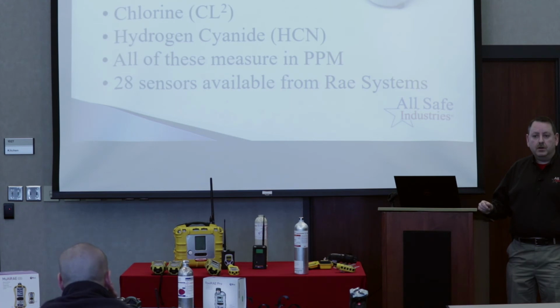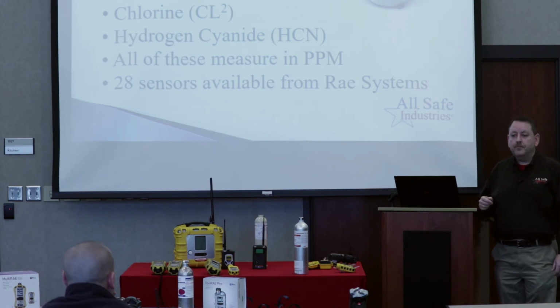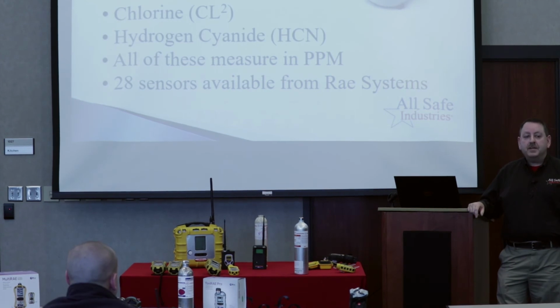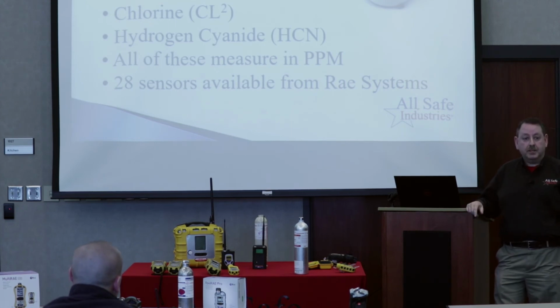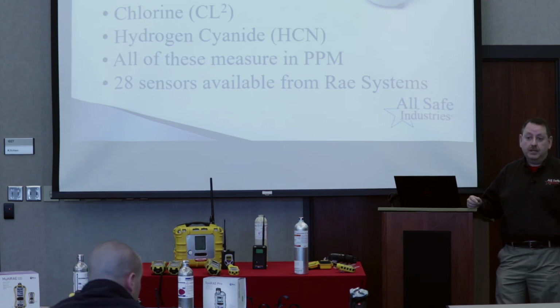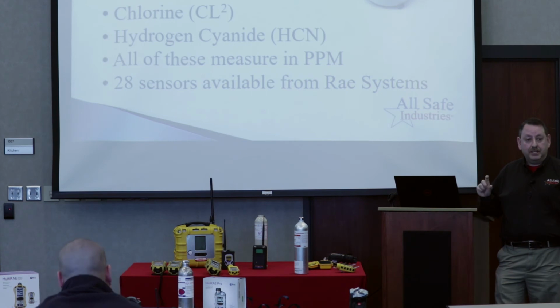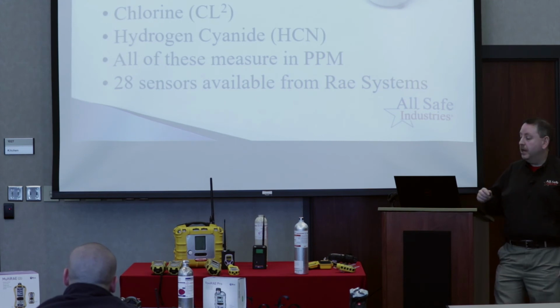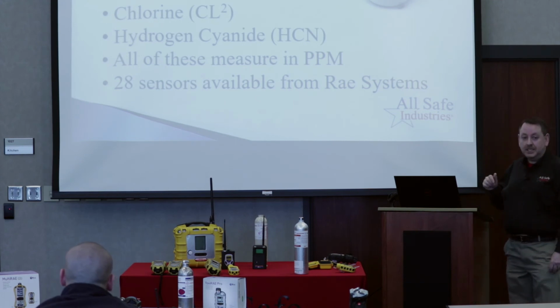Why would that be important to know, oxygen enrichment? Because everything burns in an oxygen-enriched atmosphere. So even your turnout can burn in an oxygen-enriched atmosphere. That's why we use O2 and acetylene on a torch setup, because it's a very hot burn that can cut through metal. So if your oxygen values rise above 23.5%, you're going to get a high oxygen alarm. And again, that can be as dangerous as low oxygen, okay? So again, the oxygen sensor reads in percent. It starts at a number, and it can go down and go into alarm, or it can go up and go into alarm.